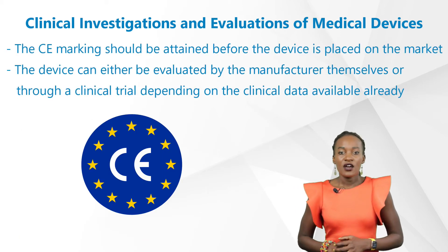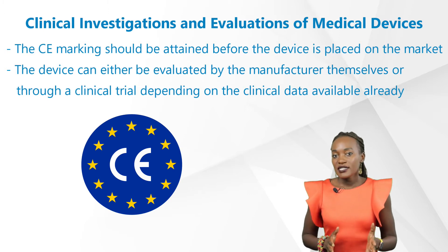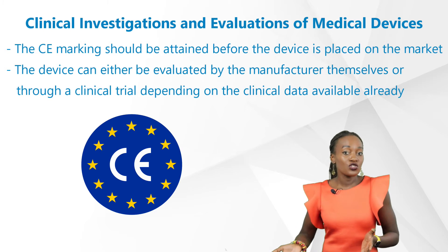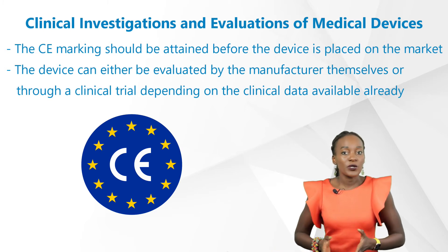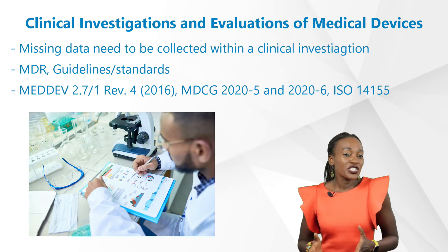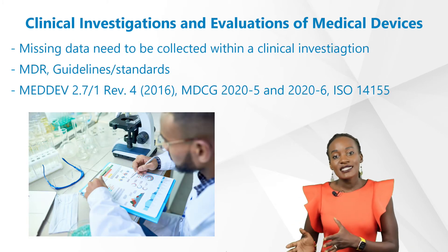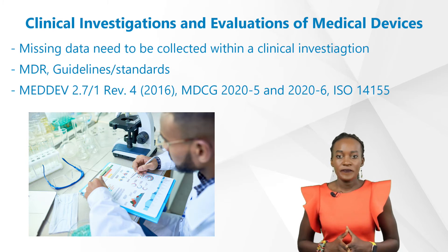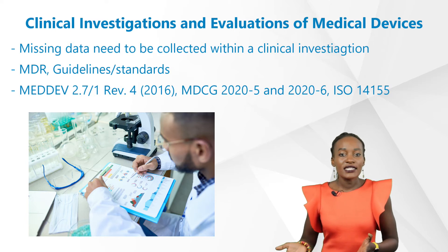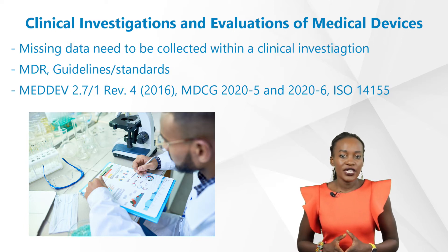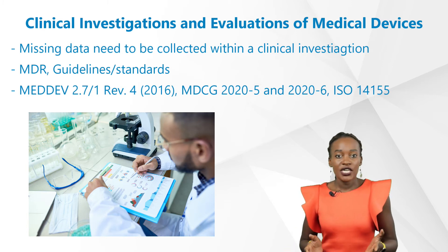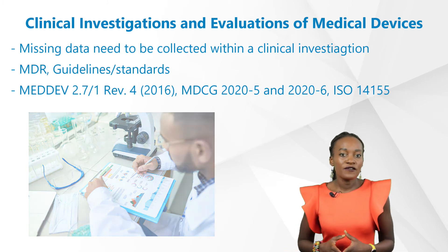CE marking should be attained before the device is placed on the market. For this to happen, the device can either be evaluated by the manufacturer themselves or through a clinical trial, depending on the clinical data already available. If no clinical data is available, the evaluation cannot be done, and the missing data must be collected within a clinical investigation. Several requirements such as MDR guidelines and standards must be observed when creating the clinical evaluation, including those from MEDDEV, MDCG, and ISO 14155.